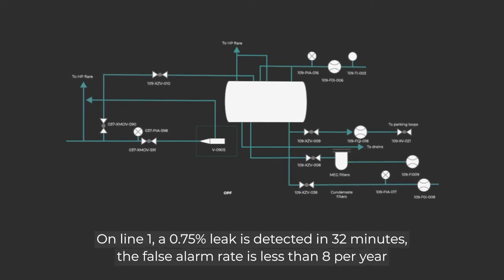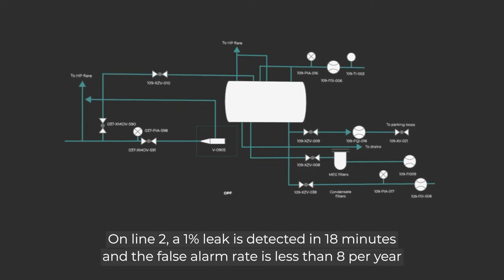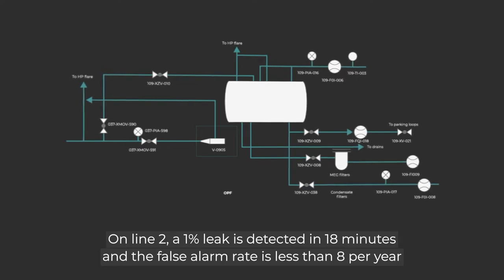On Line 1, a 0.75% leak is detected in 32 minutes, with false alarm rate less than 8 per year. On Line 2, a 1% leak is detected in 18 minutes, with false alarm rate less than 8 per year.